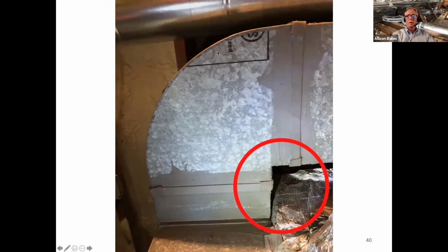A lot of people are looking at this nice curve, but this is really what determines whether it's a good fitting or not. And here's how you can think about that. Have you ever seen a racetrack, NASCAR, Indy, whatever, where they have sharp 90-degree turns? No, because what would happen, think about the air as race cars going through here. If the air is coming through this way and it's got to make this turn, is it going to just make a sharp 90-degree turn? No, it's going to shoot out this way and then turn, which means there's going to be a bunch of turbulence in here. And so this air is going to crash into the air coming down here. So it's a mess. So you don't want a sharp throat.